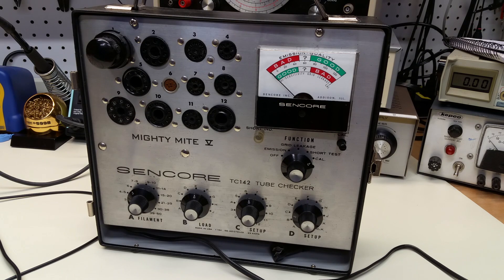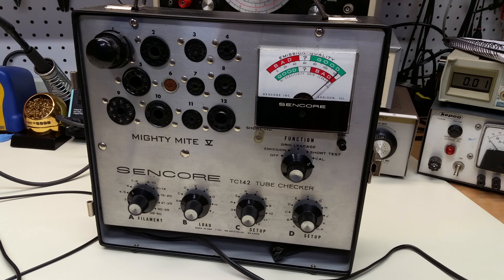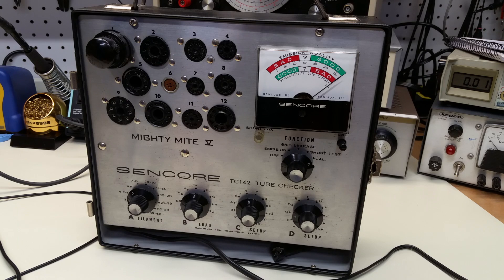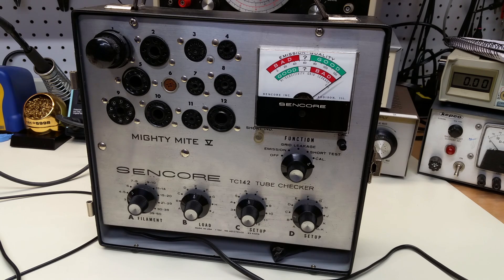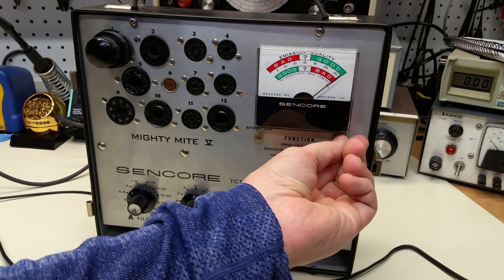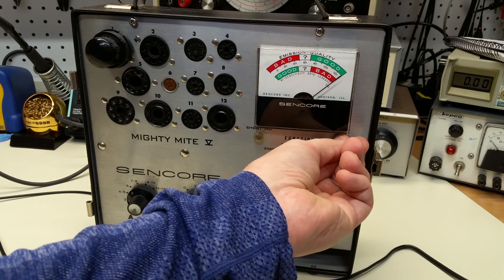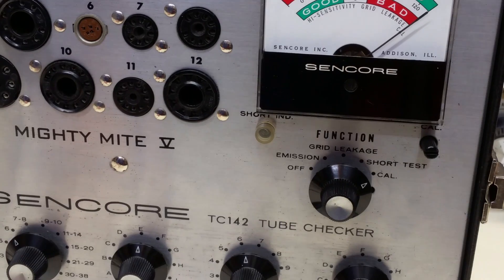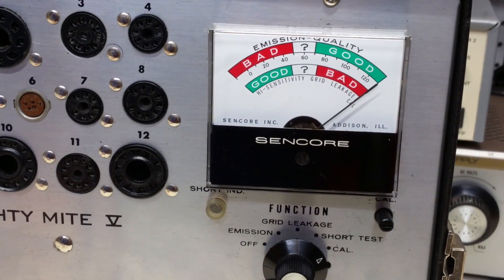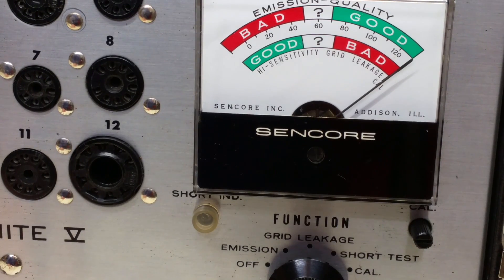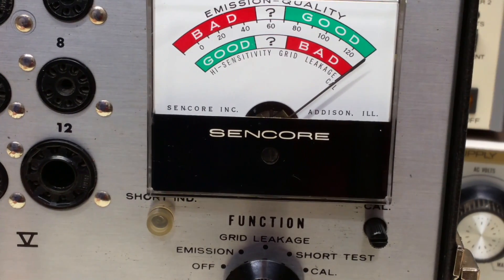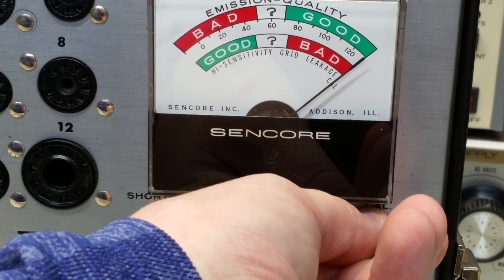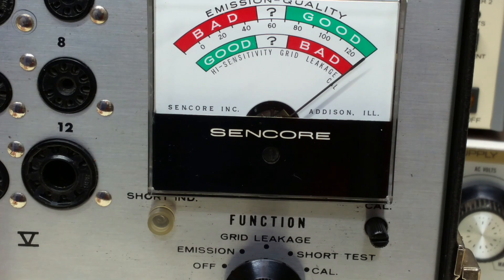And the way you do this is you turn it on, and you have a calibration setting right here, which essentially is kind of the equivalent of a line control or a line setting function. And so you peak it up, you get it over right so that it's in line with the rightmost calibration line on the meter. And I'm going to blow this up here just to see if we see what I saw. So let me just peak it up a little bit more. All right, so there it's pretty well in line. And we're just going to watch this.